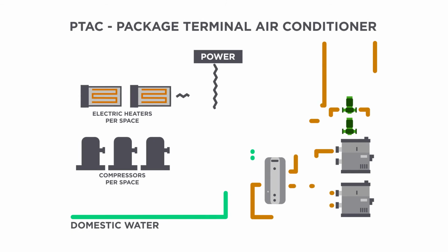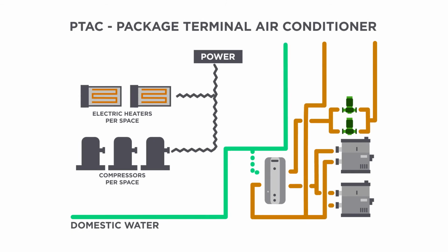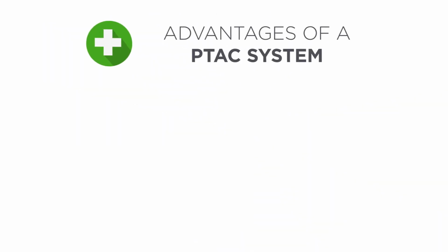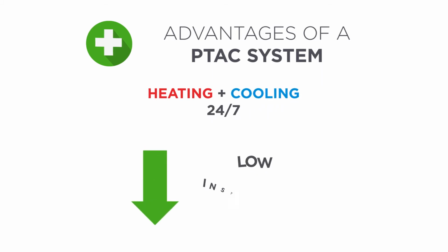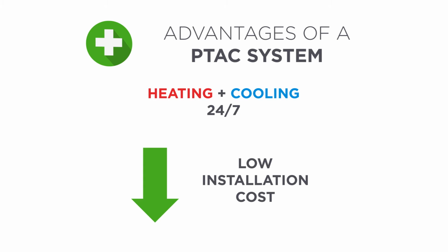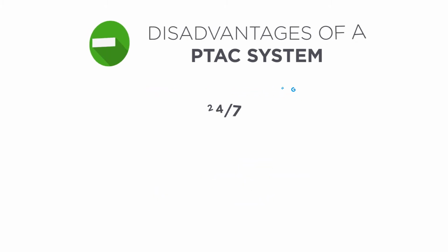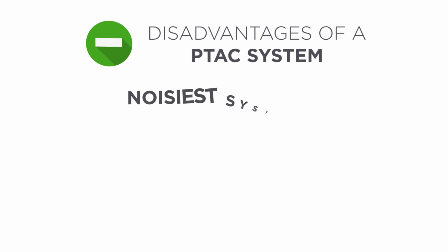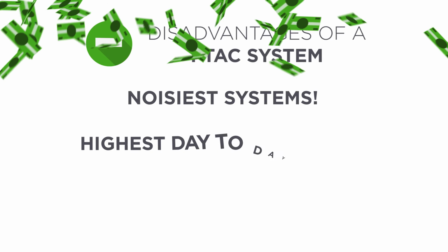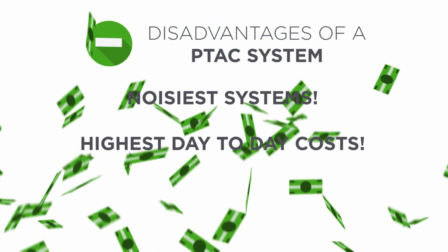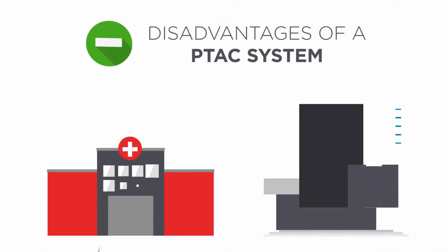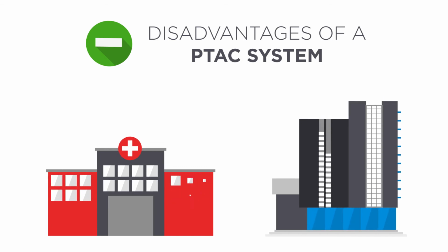The last system of choice is the infamous PTAC, a packaged terminal air conditioner, also known as the window shaker. The advantage of this rudimentary system is that these PTACs will provide heating or cooling 24/7 to the tenant, and it has some of the lowest installation costs of any system on the market. But the disadvantages of this system far outweigh any advantages it may claim. PTACs are not only the noisiest systems, but have the highest day-to-day costs to operate, creating significant issues in situations like hospitals and hotels where the operator is footing the electricity bill.